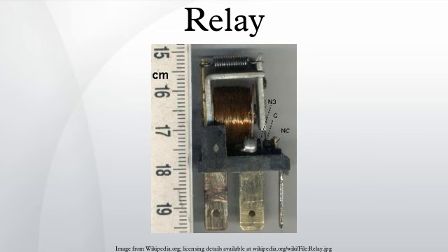Normally closed contacts disconnect the circuit when the relay is activated. The circuit is connected when the relay is inactive. It is also called a Form B contact or break contact. NC contacts may also be distinguished as late break, or NCLB, which means that the contacts stay closed until the button or switch is fully disengaged.